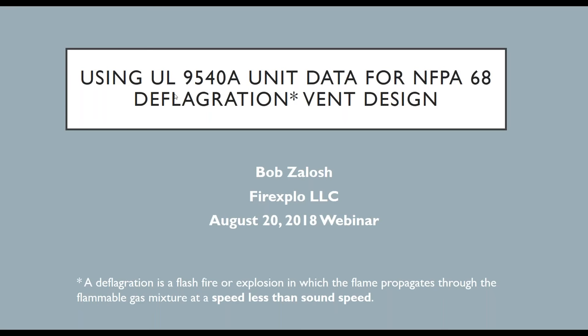Thank you, Alfonso. In the interest of time, I'm going to run through the more visual aspects of this, but cut short the technical equations and details of the vent design. So the basic idea is to determine how much vent area is needed and other vent parameters to prevent unacceptable damage to the enclosure during a deflagration.